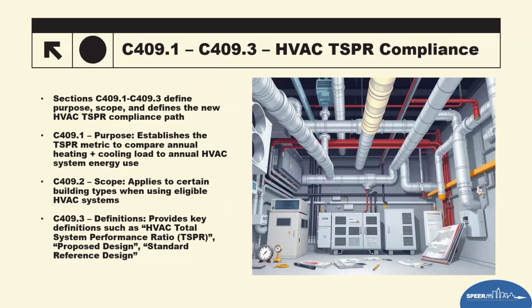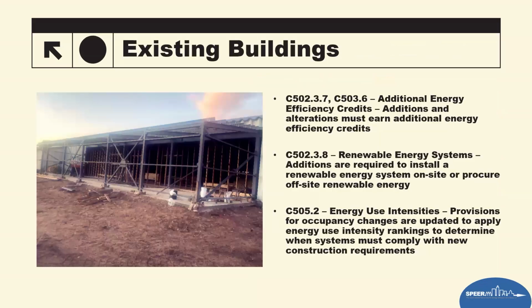And then there's something new to this, which is basically HVAC TSPR compliance. I think on the next section I'll go through what that means. So this section basically introduces a major shift in how they can achieve compliance with the IECC. Rather than just meeting the component efficiencies, this path is going to ask how much annual heating and cooling load you serve versus how much energy the HVAC system consumes. So if you're in an applicable building, in other words, if your building's not exempt from this, and your HVAC system falls under an eligible list, you need to choose from paths. Basically, you need to understand the definitions, what it needs to look like, and then make sure your simulation methodology is correct, and then model both the proposed system and the reference system accurately. So it's a performance-based approach that promotes holistic system efficiencies rather than piecemeal component compliance. It's another way of looking at the efficiencies.